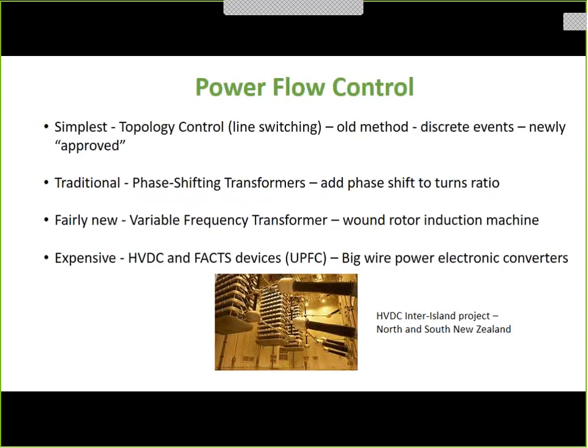Okay, here's an example of some of that. There's a popular thing now called topology control. It used to be sacred. You don't open up a line. It's wear and tear on the circuit breakers. It causes a big disturbance that wears on the grid. So you were not allowed to open or close the transmission line unless it was an emergency.